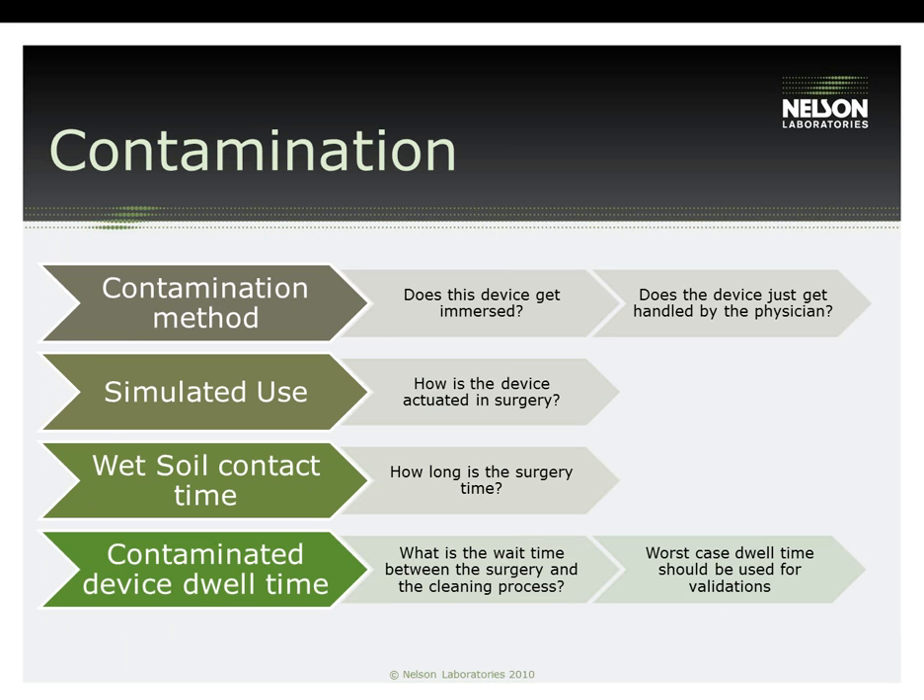After the test soil has been determined, it is time to define the contamination process. How is the device utilized in surgery? Does it get immersed? Does it get handled by the physician? Does it see spray from body fluid, or a combination of these actions? Is the device actuated during surgery? Is the device used and/or actuated and set aside several times throughout the surgery? Next, determine how long the surgery time is so that the device dwells in the contamination fluid for the correct amount of time. Finally, how long is the time between the patient procedure and when the reprocessing begins? Does the test soil dry on the devices? The most important thing to remember is to set up a test plan so that it mimics the worst possible scenario in the clinical setting.